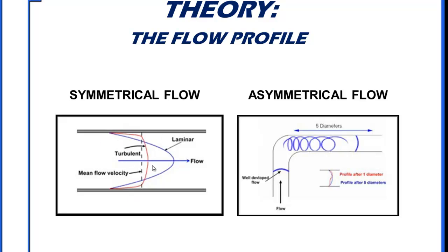These different elliptical shapes are referred to as Reynolds numbers, and they'll change throughout the range of low or high flow. But one thing that is common between the different blunt and more pointed shapes is that if you drew a center line down the center, the top half of flow would equal the bottom half of flow. This type of condition normally exists in applications where you have your 10 to 15 diameters of straight run of pipe at flows around 10 feet per second. Higher flow rates, more straight run of pipe. Lower flow rates, less straight run of pipe is required to meet this requirement.